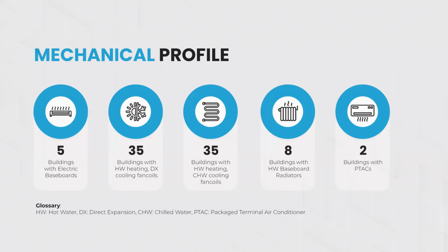They've typically done that in their smaller buildings, talking 5 to 6 stories. Their larger buildings, for the most part, are hot water heated, chilled water cooled 2-pipe fan coil systems - very traditional, very straightforward, and very typical for older apartment buildings. Although 2-pipe hot water heated, chilled water cooled systems do not offer simultaneous heating and cooling every hour of the year, which is one of the downsides, it's a very traditional type of build.